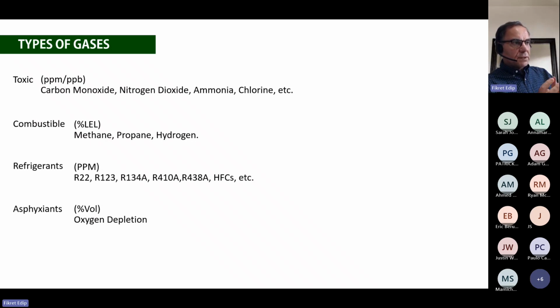The fourth one is asphyxiant. Asphyxiant gases are measured in percent volume, and they can cause oxygen depletion. You may have seen oxygen sensors in MRI rooms in hospitals. Why would they put oxygen sensors there? Because of the noble gases they use to cool down the MRI machine, because it gets very warm. Although those noble gases are not toxic, if they leak out, they deplete oxygen in the environment very quickly.